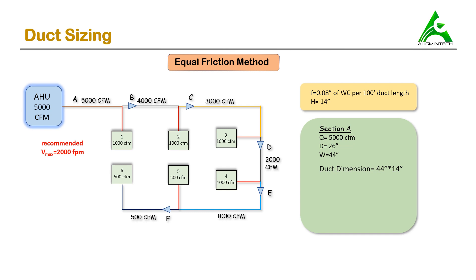The job is not done yet — we need to check the aspect ratio. The aspect ratio is the ratio of duct width to duct height and must lie between 1 and 4 per standards. In our case, 44 divided by 14 gives 3.14, which is less than 4, so this is accepted. Therefore, the final duct size for section A is 44 inches by 14 inches.